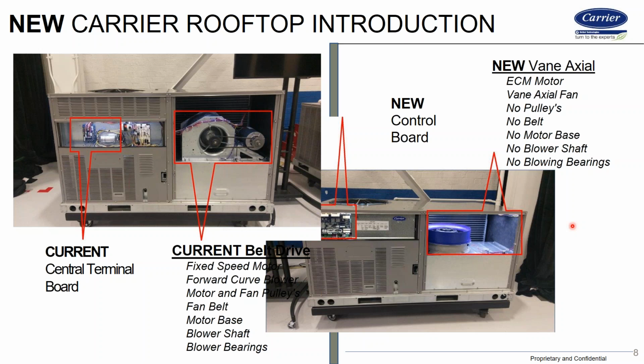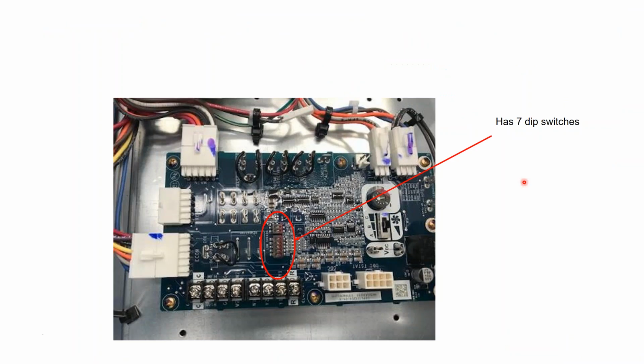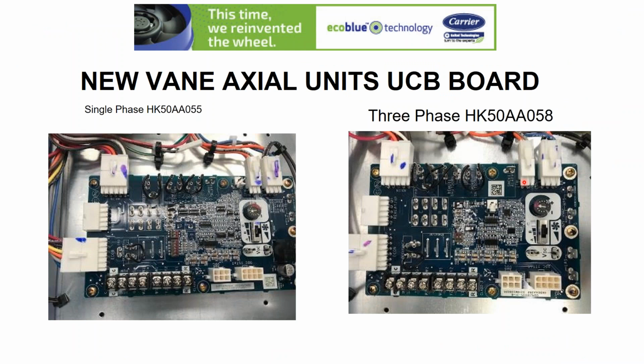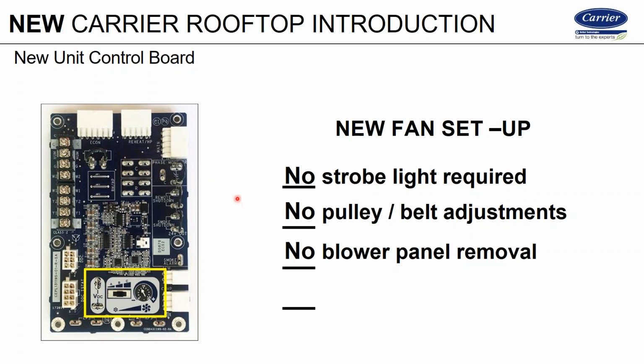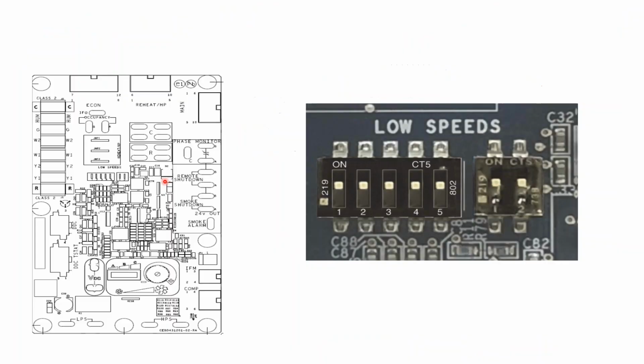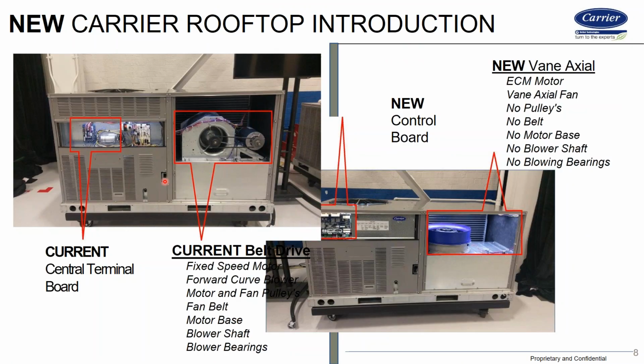All right. Clinton asks, on these EcoBlue units, is there any power protection? He's comparing them to some of the larger, like 10-ton units that have VFDs, where City of Chicago power quality is causing an issue. So he's asking if there's any power protection on these small ECM-driven units. The only thing we have is a phase monitor on the 3-phase. That's right here. So you pop that off and hook your phase monitor up. That's an accessory. That's not standard. So we do have phase monitoring, and that's a good question to segue into my next conversation. That is about 3-phase power on these that we're starting to get feedback and identify some problems.